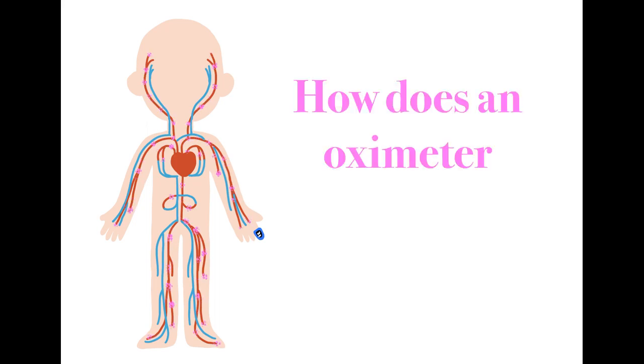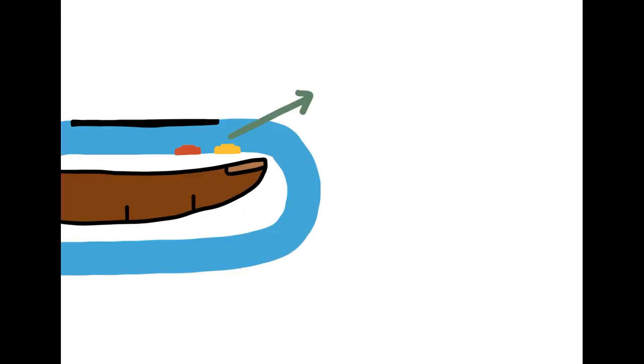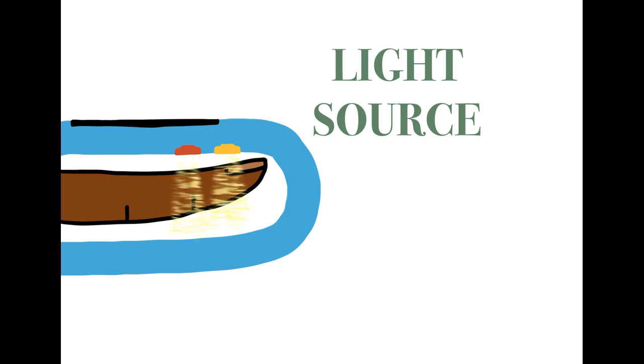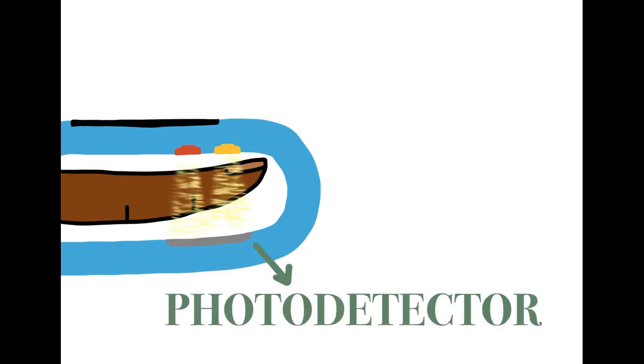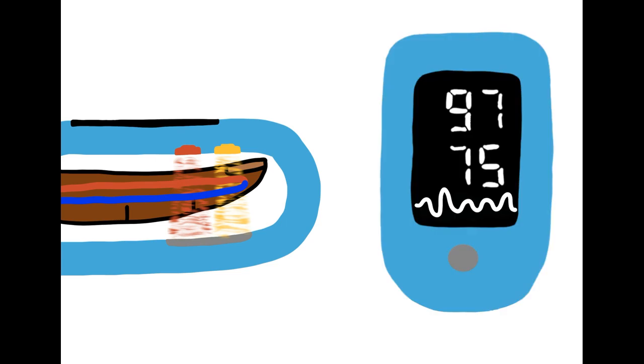But how can an oximeter measure your oxygen levels? A pulse oximeter has two components to its device: a light source that emits light, and a photodetector, the part that receives the light when turned on. The light source passes through the finger placed in between the oximeter. Some of this light gets absorbed by the finger, while the rest reaches the photodetector. The light source emits two different wavelengths of light. These lights affect blood with oxygen and blood without oxygen differently. This allows the device to measure the amount of oxygen in the blood.